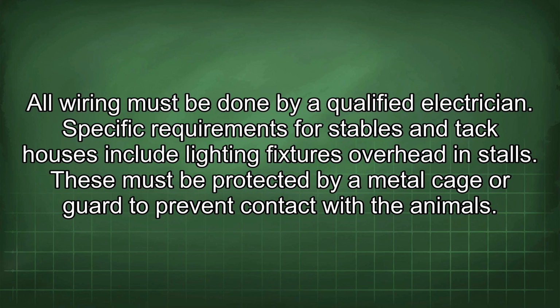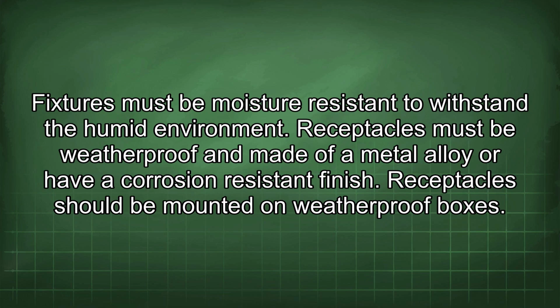Specific requirements for stables and tack houses include lighting fixtures overhead in stalls. These must be protected by a metal cage or guard to prevent contact with the animals. Fixtures must be moisture resistant to withstand the humid environment. Receptacles must be weatherproof and made of a metal alloy or have a corrosion resistant finish. Receptacles should be mounted on weatherproof boxes.